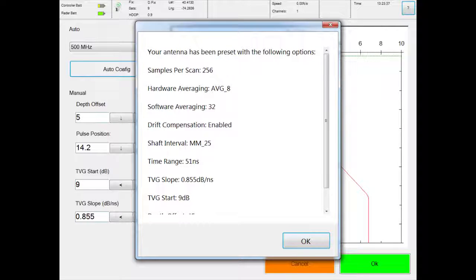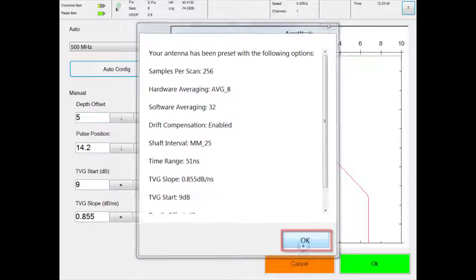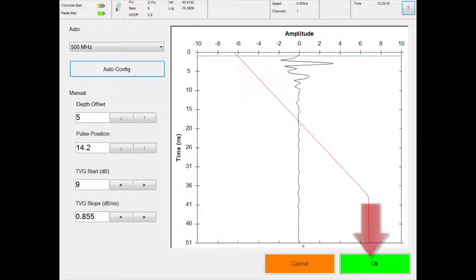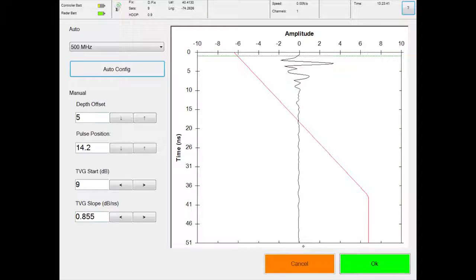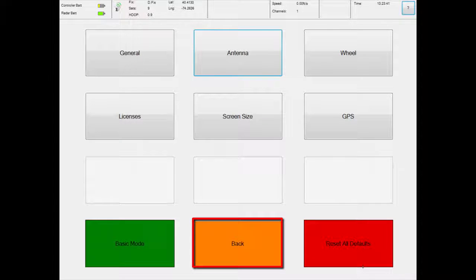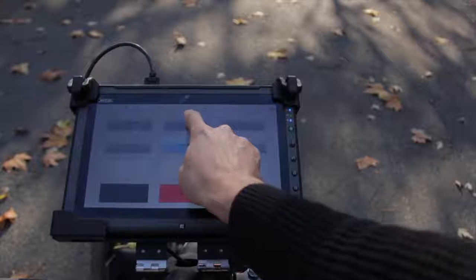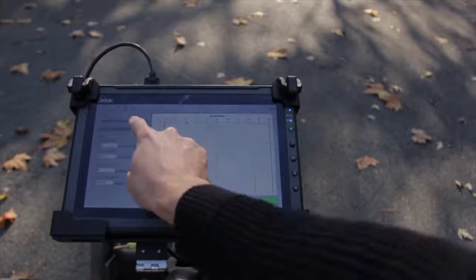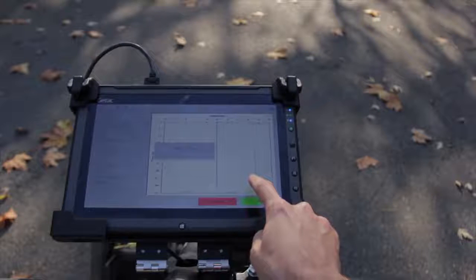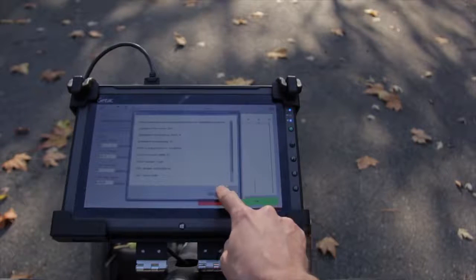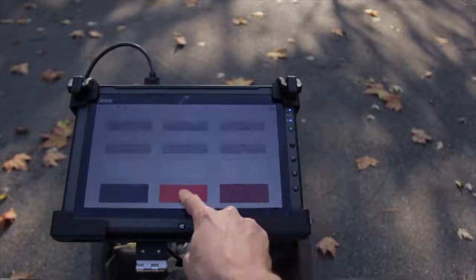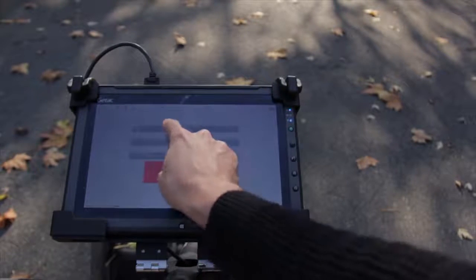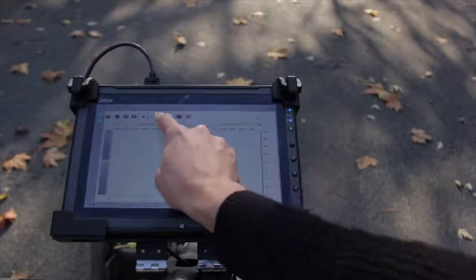Press the OK button at the bottom right to return to the settings menu. Touch the back button to return to the main menu. Remember to auto configure antenna settings before commencing work at each new site. This will allow the antenna to adjust to its environmental conditions and allow for better data collection.